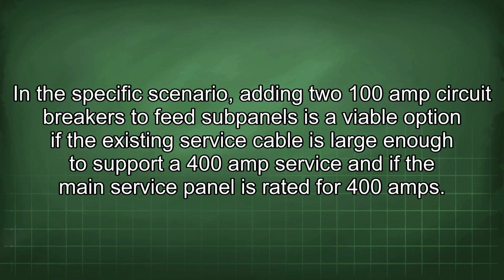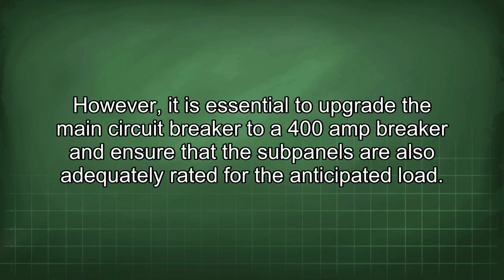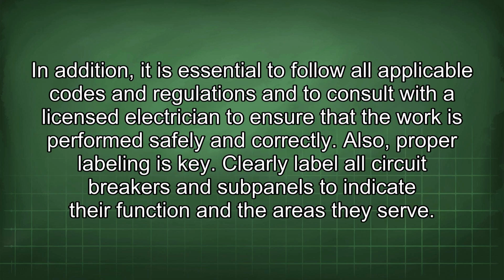In a specific scenario, adding two 100-amp circuit breakers to feed subpanels is a viable option if the existing service cable is large enough to support a 400-amp service and if the main service panel is rated for 400 amps. However, it is essential to upgrade the main circuit breaker to a 400-amp breaker and ensure that the subpanels are also adequately rated for the anticipated load. In addition, it is essential to follow all applicable codes and regulations and to consult with a licensed electrician to ensure that the work is performed safely and correctly.